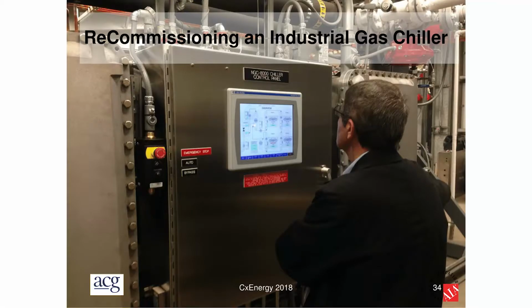We had to determine how seasonal the operation really is. Is it only in the summer, or when the sun is shining? By the way, that's what makes the gas need the chiller: the sun shining on that 17-mile pipeline gives a lot of solar gain, and it keeps the impurities suspended in the gas. So, summer, winter, we asked the question, and the operator said, well, we'd like to be able to run the thing in the winter if we have to. That's probably not during the dark months, but definitely it could be in October, and it definitely could be in March. So here's a picture of us trying to get the system running in March.